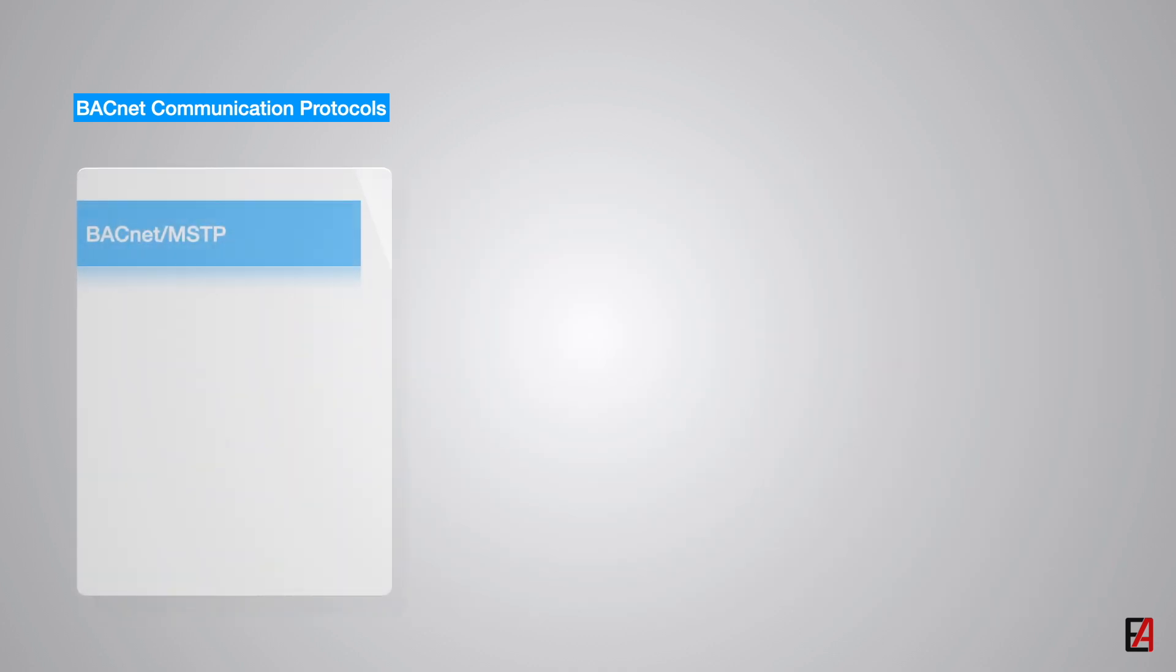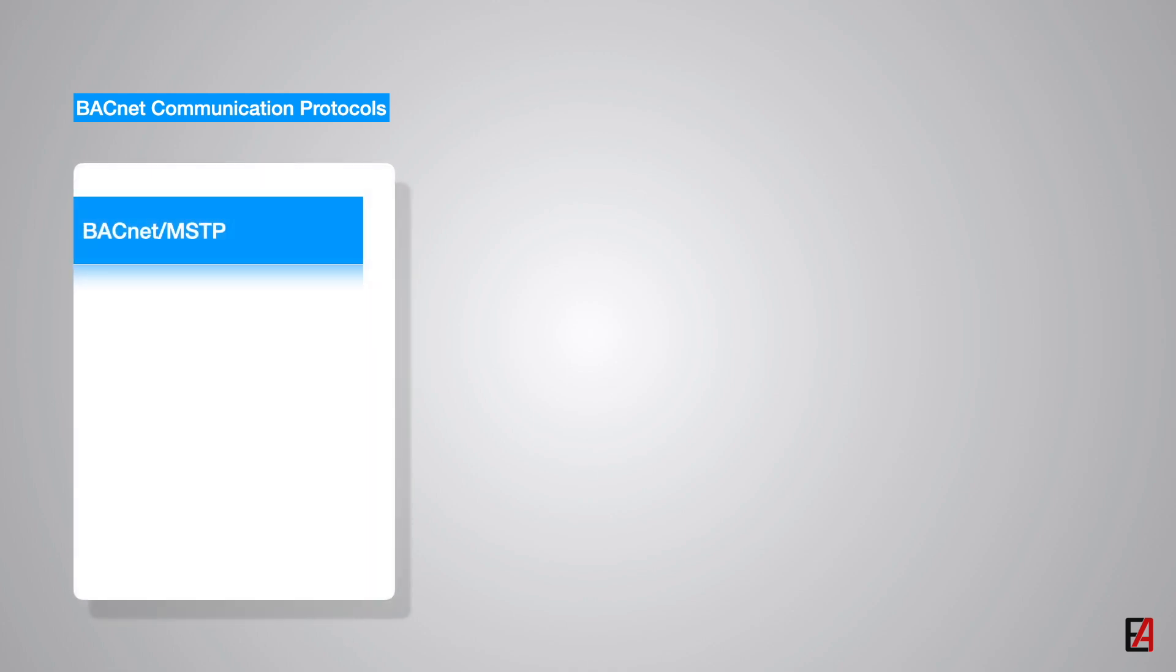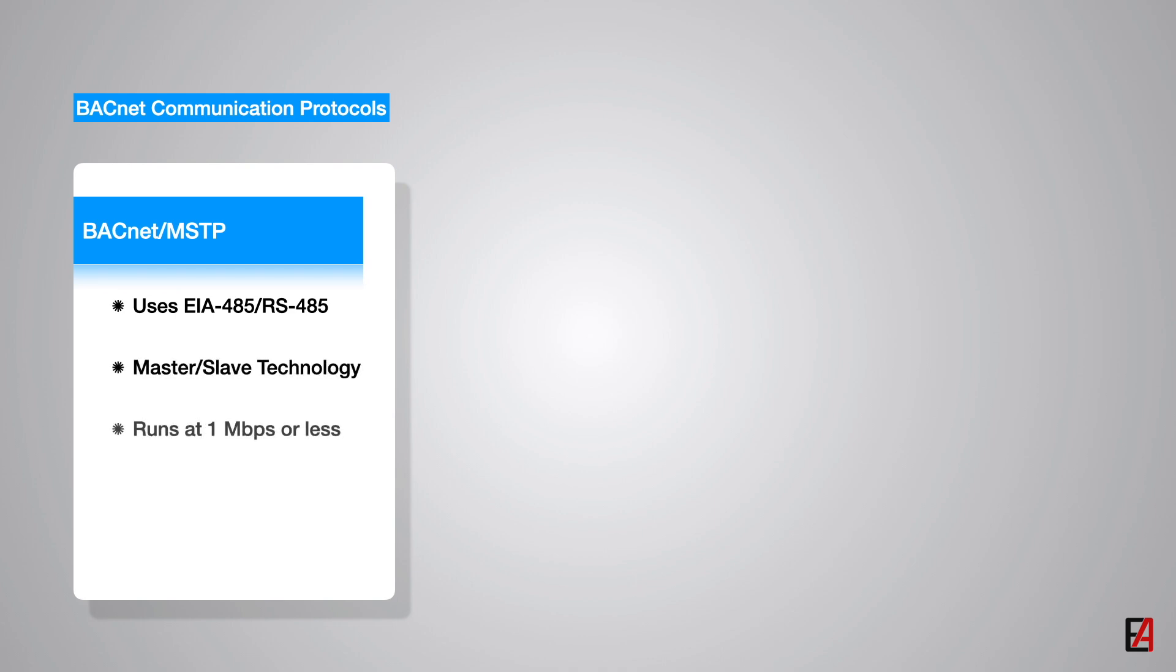The fourth networking possibility in BACnet is based on RS-485 at physical layer and master-slave token passing protocol at the data link layer. BACnet MSTP communicates at a speed of 1 megabit per second. It also offers long range communication with 1200 meters and even longer with repeaters.